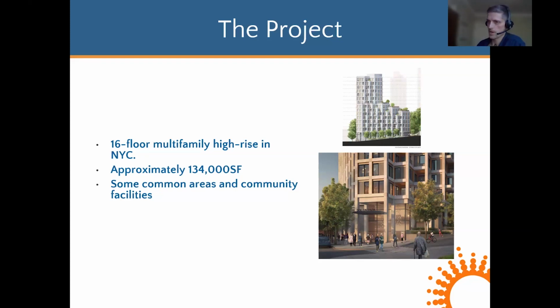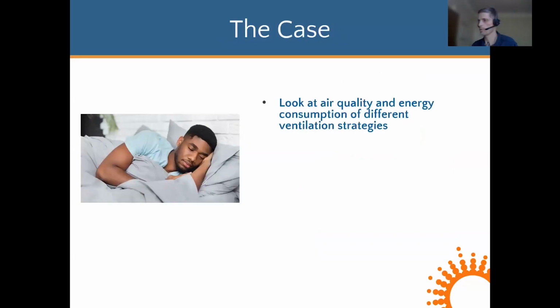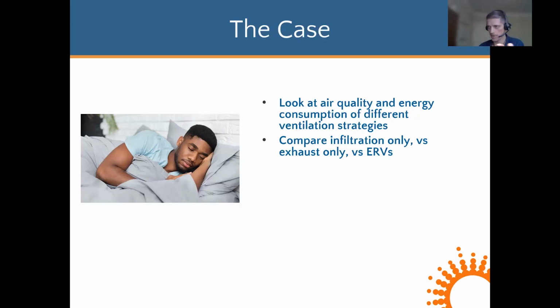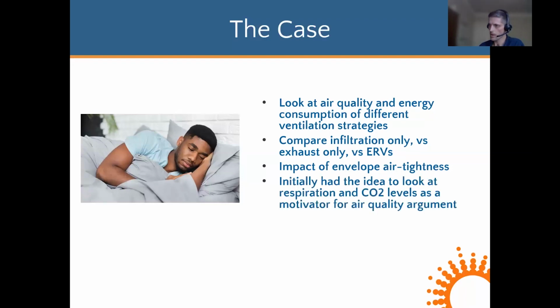So this was, at the time of design, a 16-floor multifamily high-rise, about 134,000 square feet, with some common area and community facilities. And the case we wanted to make, we wanted to look at air quality and energy consumption of various ventilation strategies. We wanted to look at infiltration only as a baseline, and then compare exhaust-only strategies versus energy recovery ventilators and show the impact of envelope air tightness on these factors. And initially, we had the idea to look at respiration and see how CO2 levels change due to respiration, if that could be a motivator to encourage better air quality. We later added filtration to the study as well.